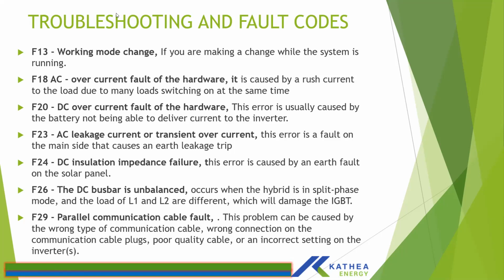And then DC bus bar unbalanced. This is most common in scenarios where you have three phase, and your inverters are not tapping from the same bus bar. Then there will be a DC bus bar unbalanced. One battery will be saying my voltage is now 48 volts, while the other inverter is saying my voltage is 50 volts. Then there is a difference between the voltages. As I've said, when wiring inverters in parallel, make sure that all inverters tap to the same bus bar, so that we avoid having a DC bus bar unbalanced alarm.